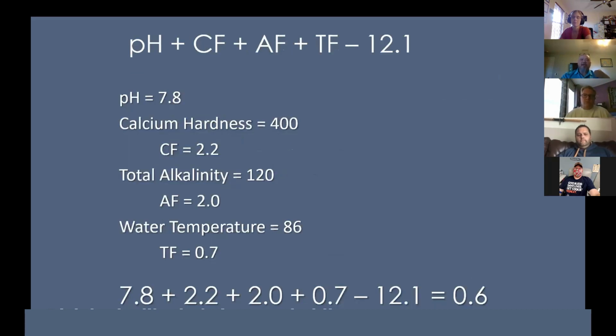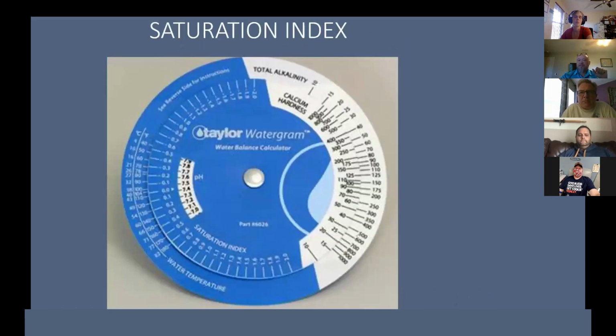So if we plug those numbers into that formula, 7.8 plus 2.2 plus 2.0 plus 0.7 minus 12.1, we get 0.6. That number being on the positive side, more than plus or minus 0.3, tells us that water chemistry is going to be on the scale forming side, and that scale will build up on the cell, and it will impact how much chlorine is being generated. The Taylor watergram, as you see there, is also another way of checking your saturation index, and it gives you a quick reference as to what your water balance is.